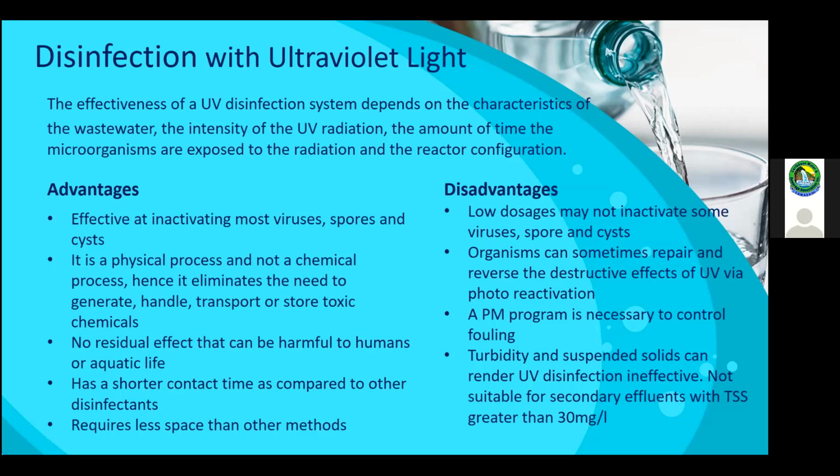So you can have organisms repairing themselves and re-existing and persisting within that environment. You will need a preventative maintenance program to control tube fouling. Tubes frequently have to be replaced because you have light bulbs being blown. The dosage is reduced after a certain number of hours of usage.